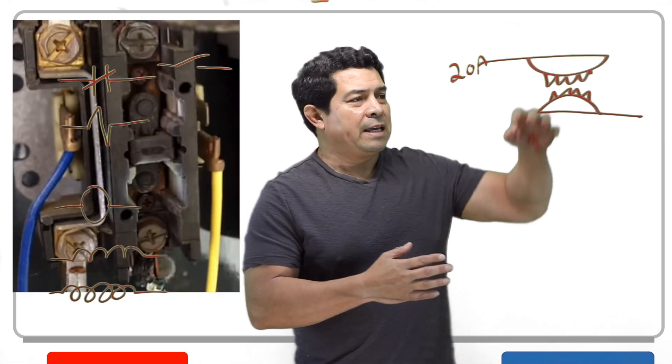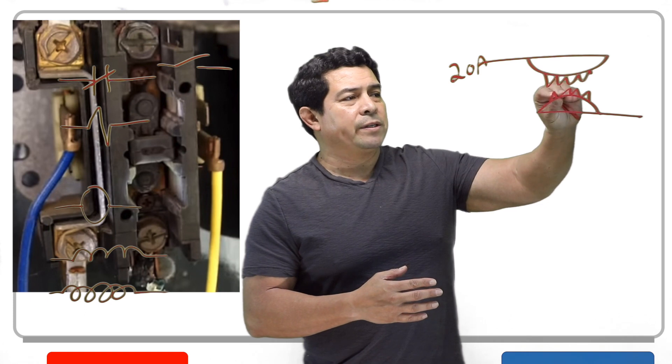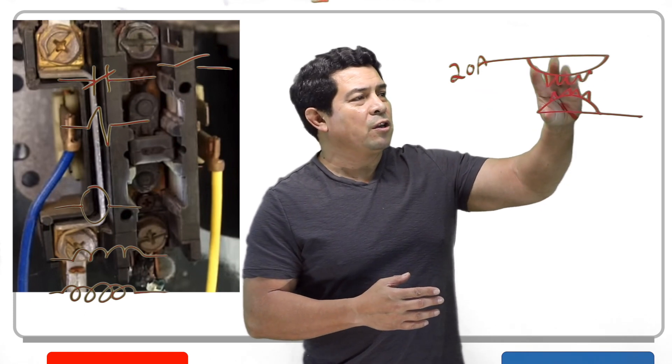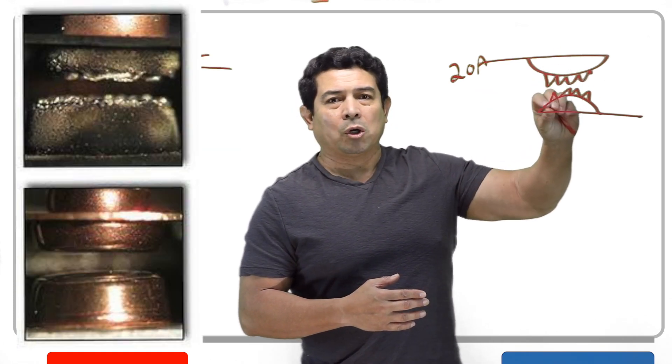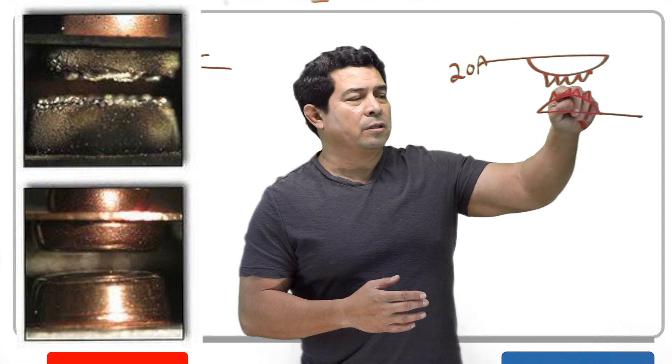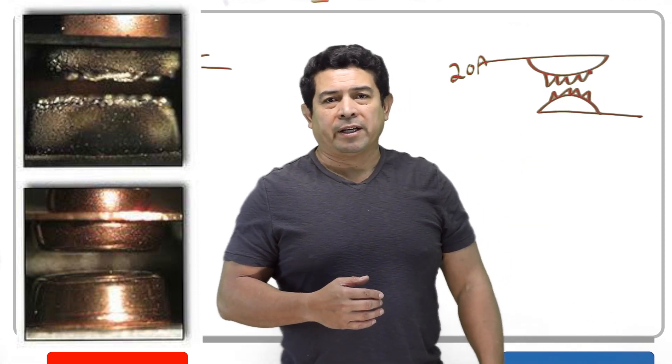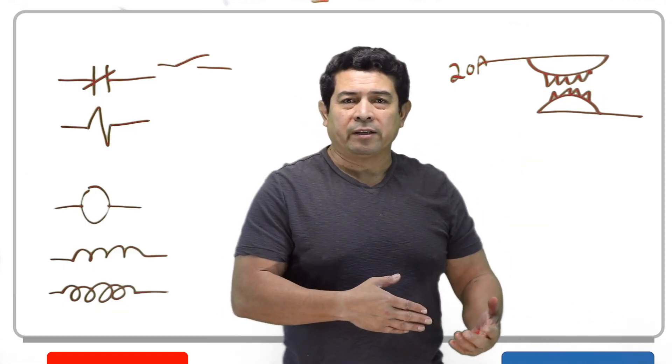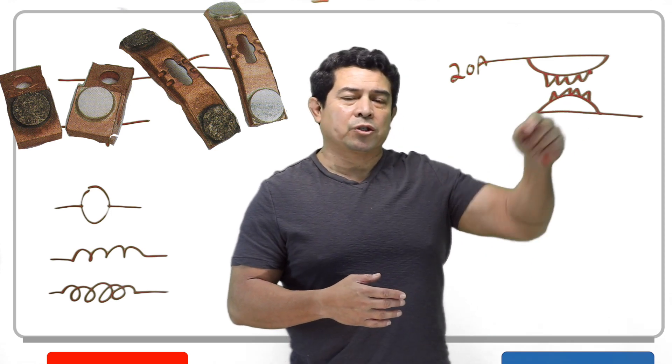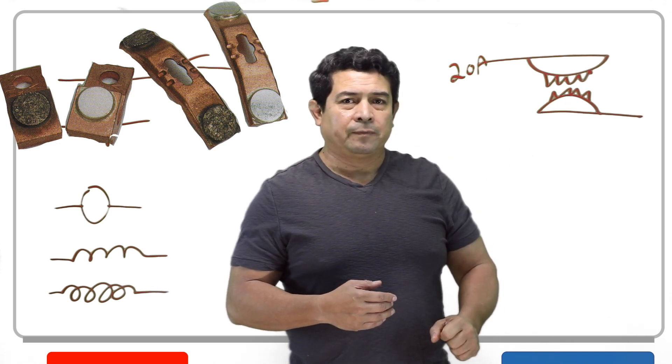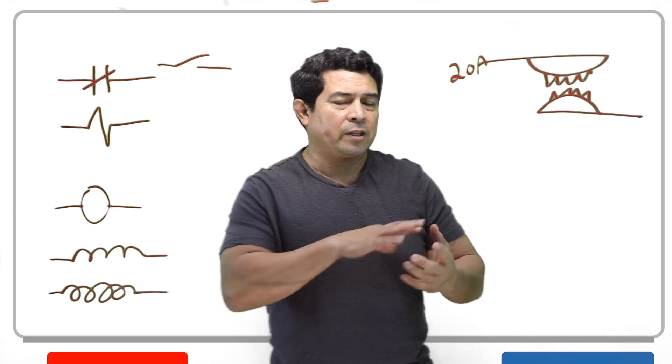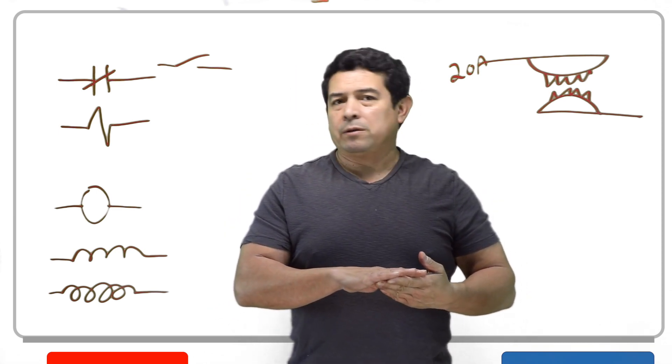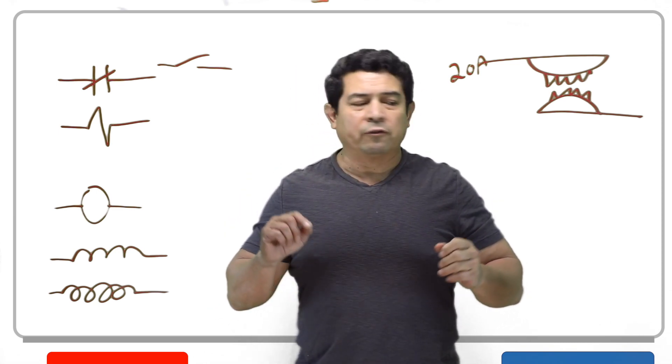So I want you to understand this because the older the contactor is or the higher the amperage, the more that this is going to arc. The more arcs, the more pitting you're going to have. The more pitting you have, the more restriction to flow that you have. Now, by looking at it, you can tell that it's pitted. But how do you know that it's actually restricting the flow?